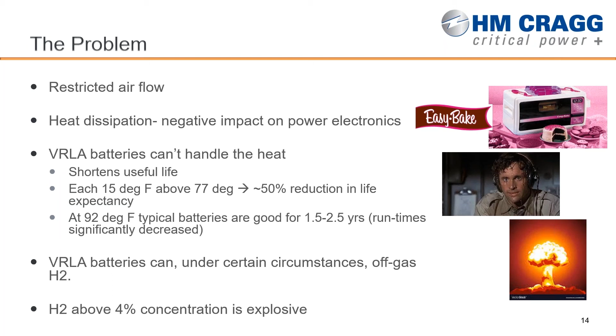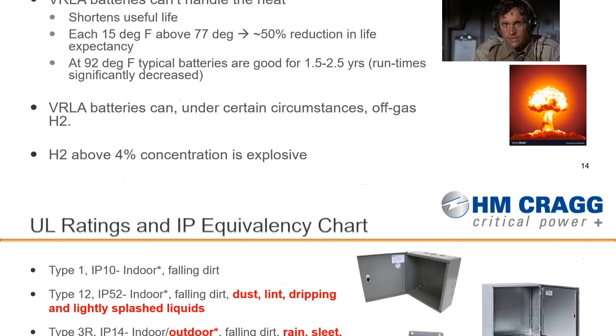VRLA batteries have another thing that we have to be concerned about, and that's that under certain circumstances, they can off-gas. They can actually vent out hydrogen. And as Cody said earlier, hydrogen concentrations above 4% can be explosive. And the last thing that we want to do is sell you a bomb. Most inspectors would take exception to that. I think you and your customers would probably take exception to that. So we need to make sure that we're mitigating and monitoring that. And as you'll see in a couple more slides here, that's exactly what we do.